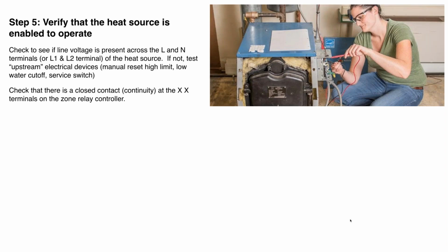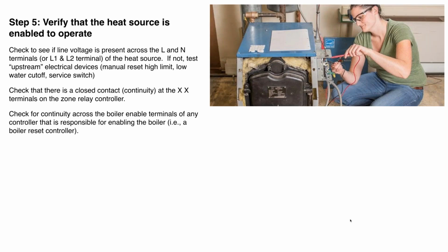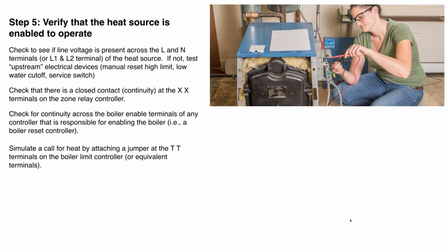In other words, the boiler is not actually receiving the call to operate if you have that type of setup, okay? Check continuity across the boiler enable terminals of any controller. It might not just be the zone relay controller. You might have a staging controller, you might have other controllers that do multiple functions that are capable of calling the boiler to operate. Check to make sure that the contacts in those other controllers are closed, giving that signal to the boiler to start.